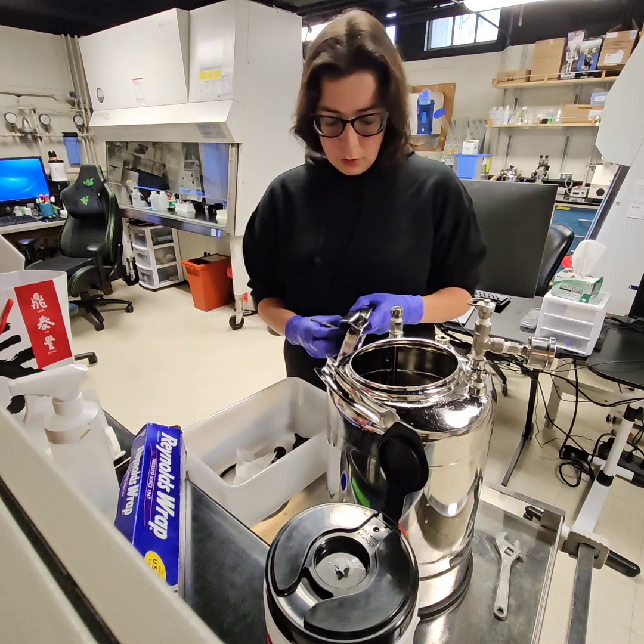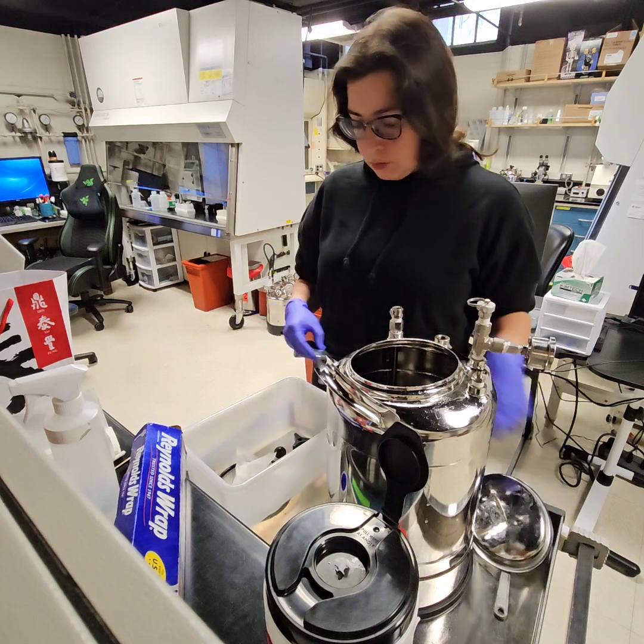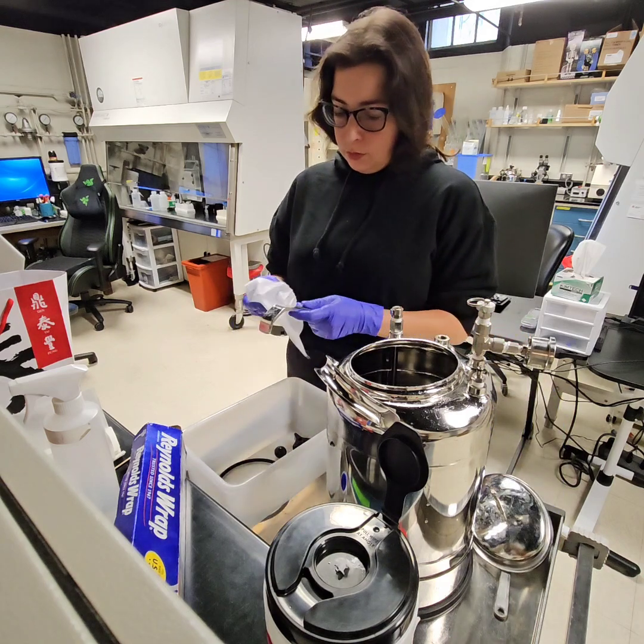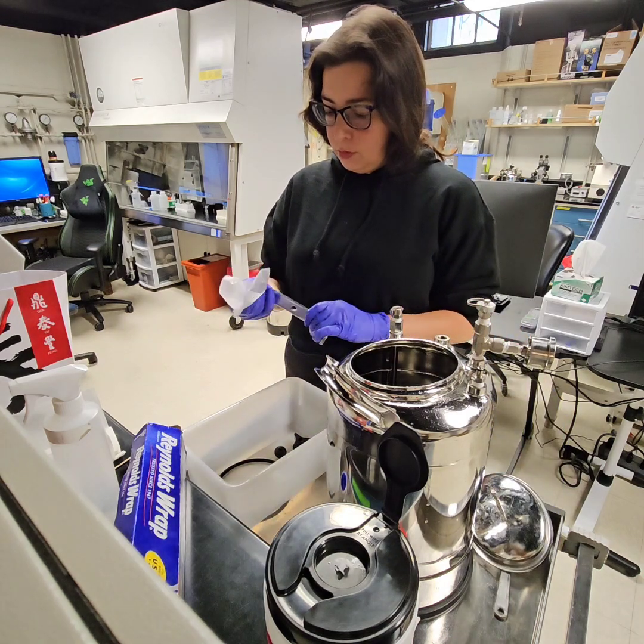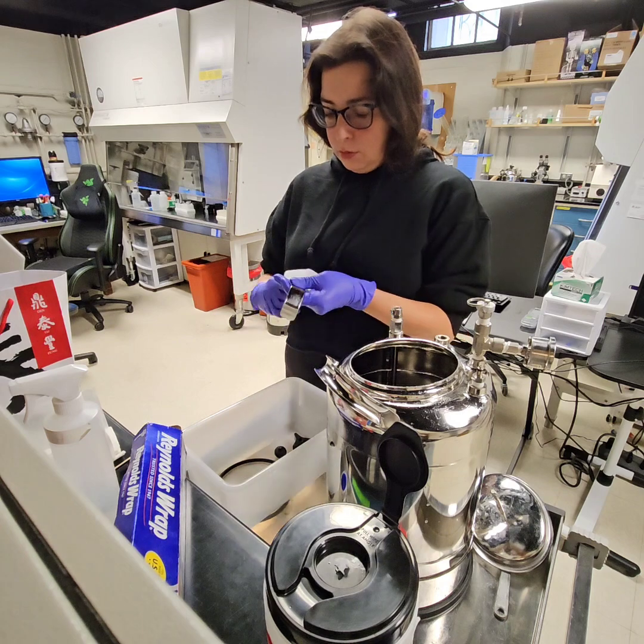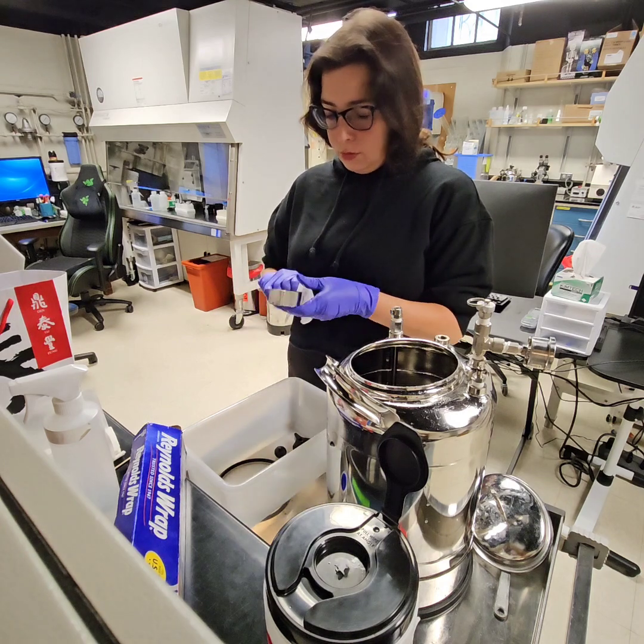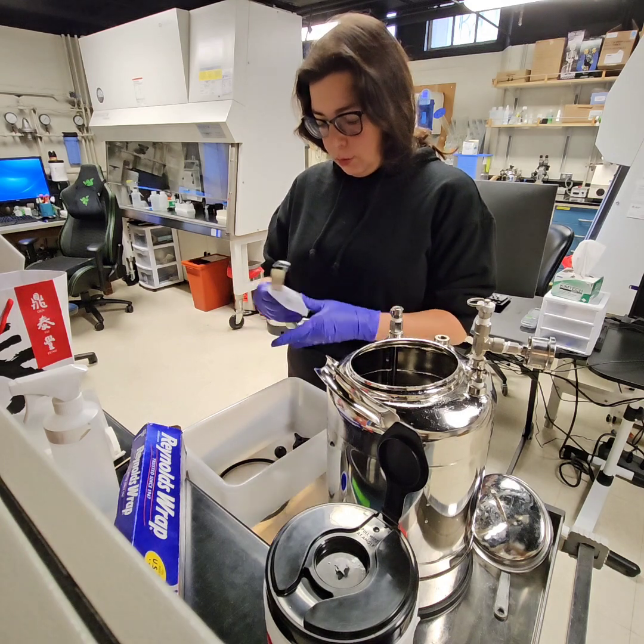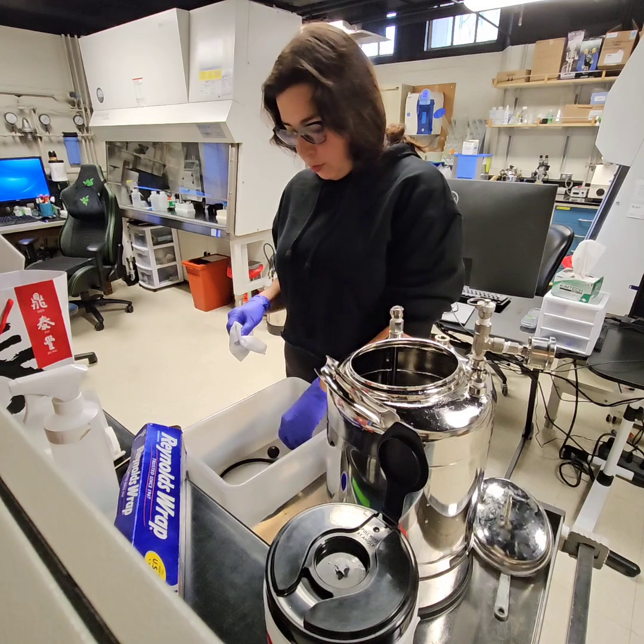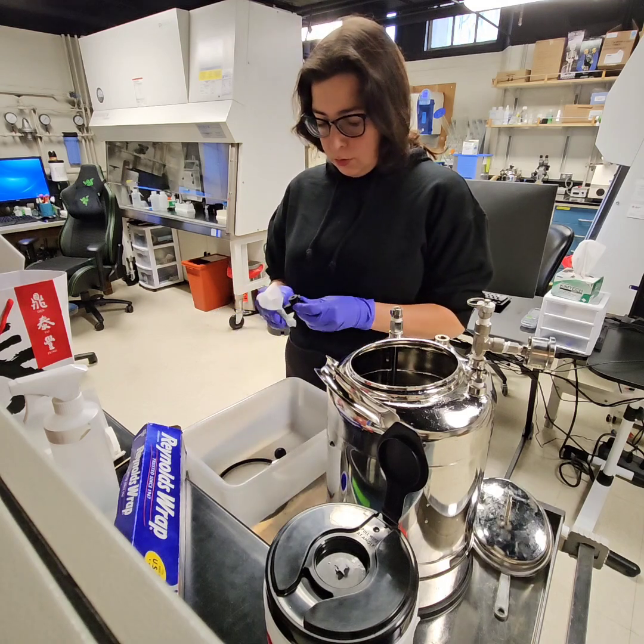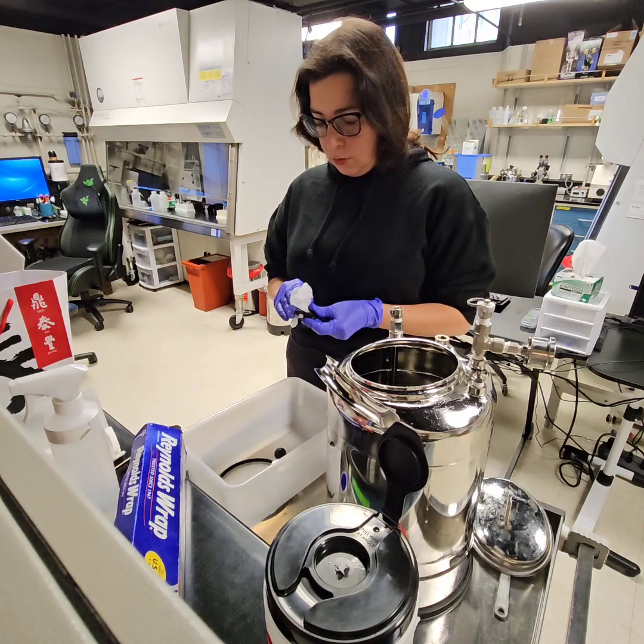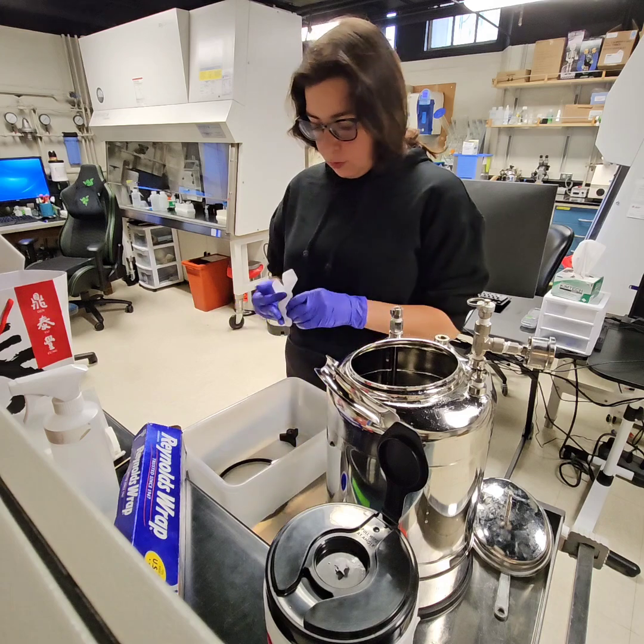And so now I'm separating both components of the lid, and now I'm going to wipe down with CaviWipes. And I'm taking care to remove any residue of sheath fluid, and you'll see that dried out. Also any dirt, because again, there are a lot of opportunities for contact while you refill the sheath tank, so that creates a lot of opportunity for potential contamination.